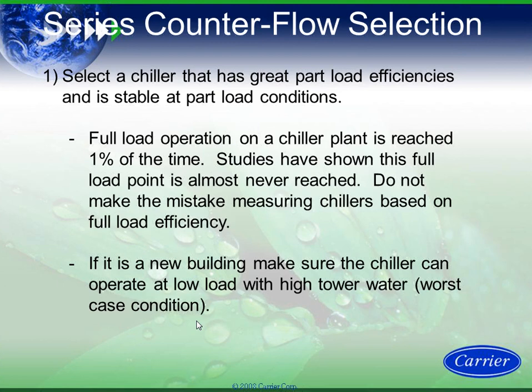So a couple of series counterflow selection criteria. I think we mentioned this before. Full load very rarely happens. Make sure when you're sizing a tower, you are able to provide low load with high tower, especially new buildings where you have a brand new chiller plant and tenants are not always all moved in yet. It needs to operate at reduced load with high tower, high lift. The 23XRV is able to do that easily. Just make sure when you're dealing with whoever you're dealing with, they are able to do that also.